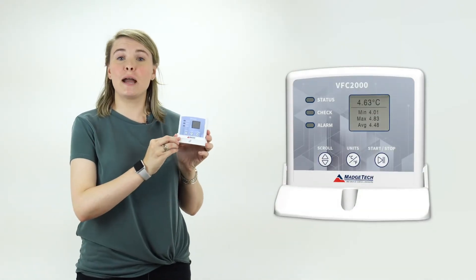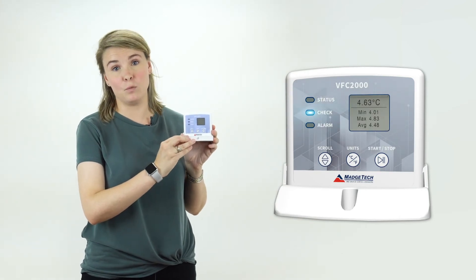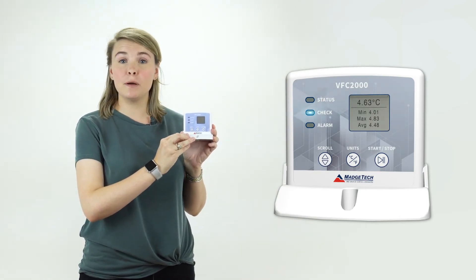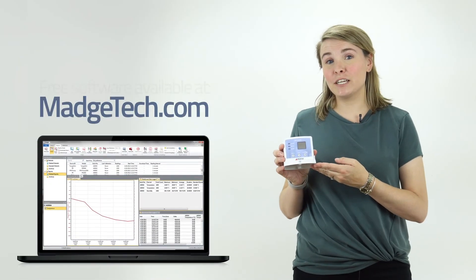The check LED reminder can also be programmed to illuminate when it's time for healthcare workers to perform daily minimum and maximum temperature checks.